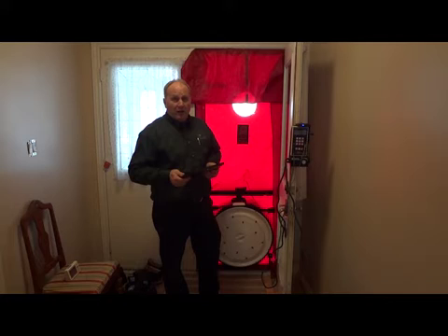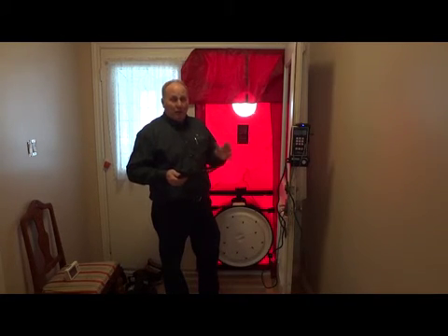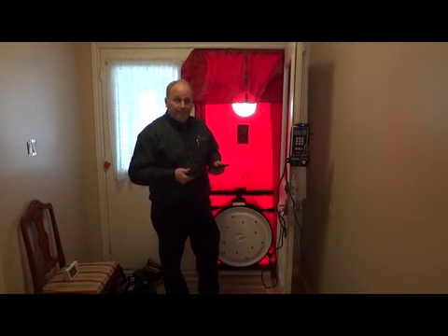Further to Tom's testing, he has an estimated leakage area of about 30 square inches. So this means if we added up all the cracks and all the air leakage in his home, it would add up to a 10 by 3, about the size of this tablet that he has, which again is very, very good. Good job, Tom.